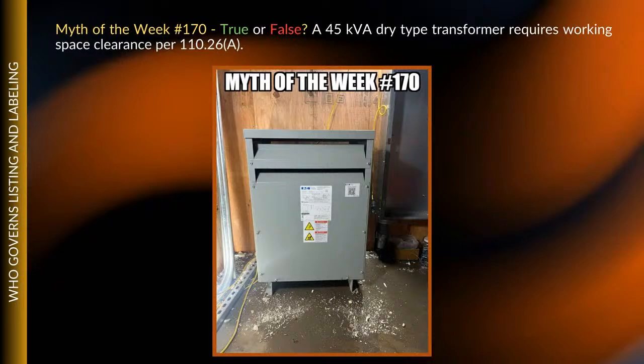One thing I want to add, James, is like this dry type transformer — are you going to have to open that cover to test voltage? No, you can test voltage right at the primary panel right there. So you're doing all the 70E, dressing correctly, verifying the absence of voltage before you even open that cover. That's why a lot of these people are confused on this one.